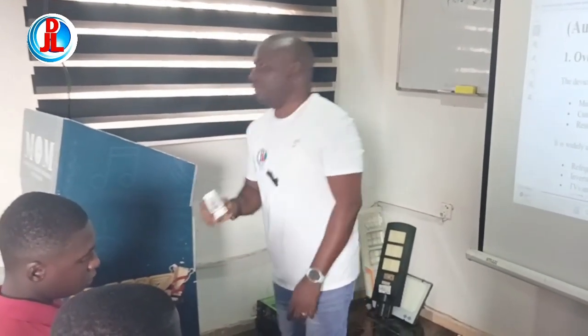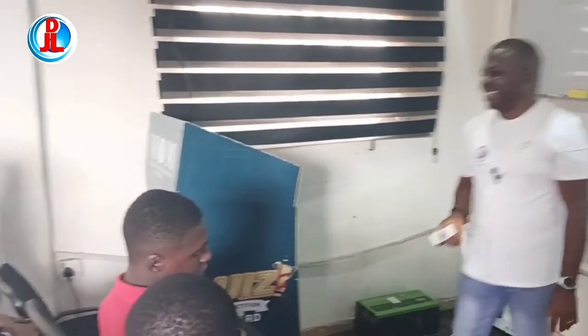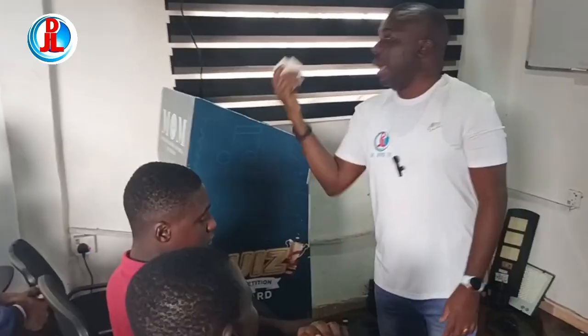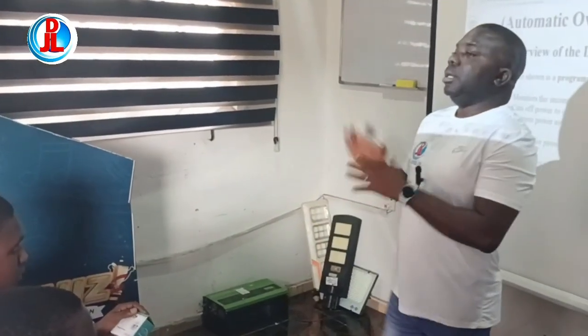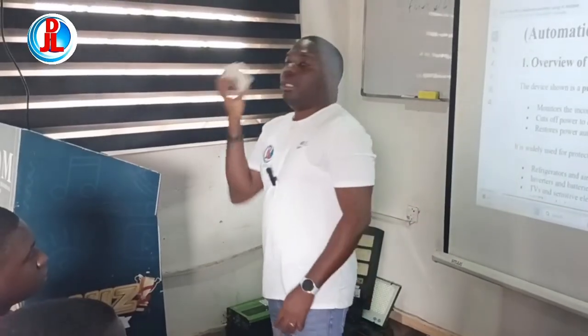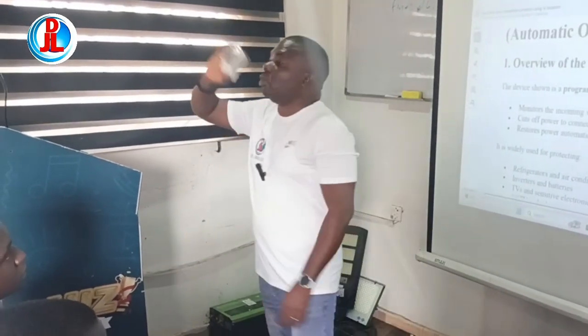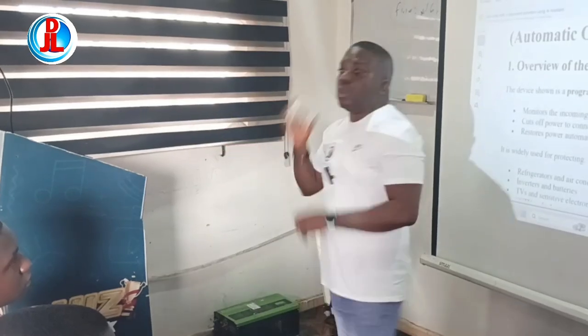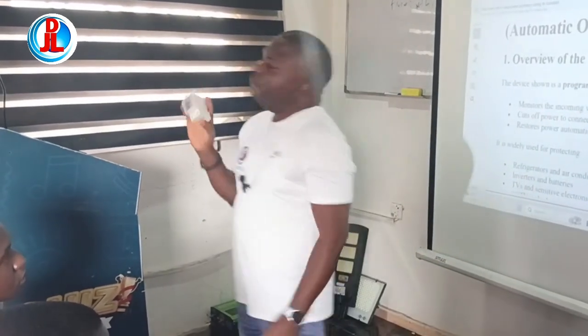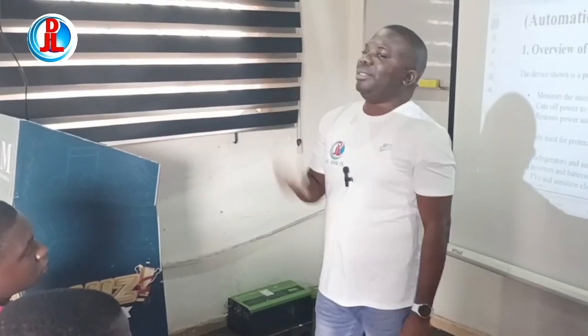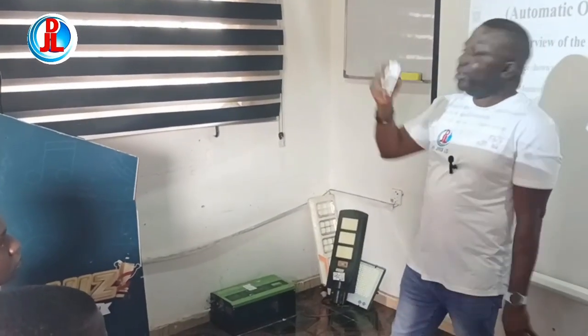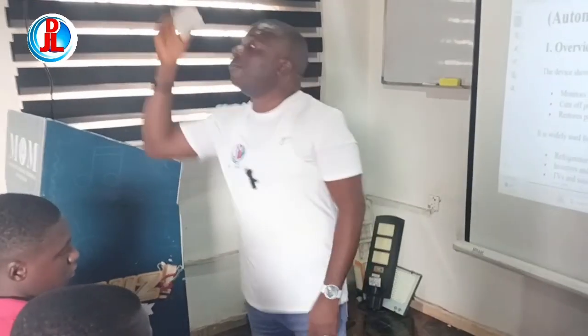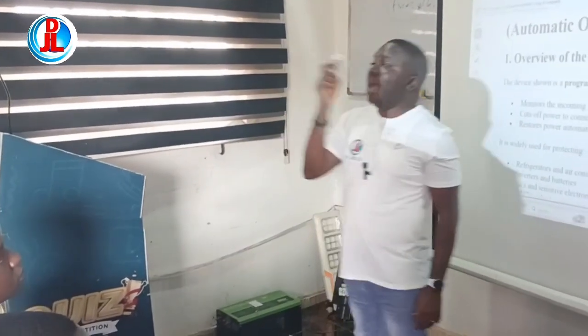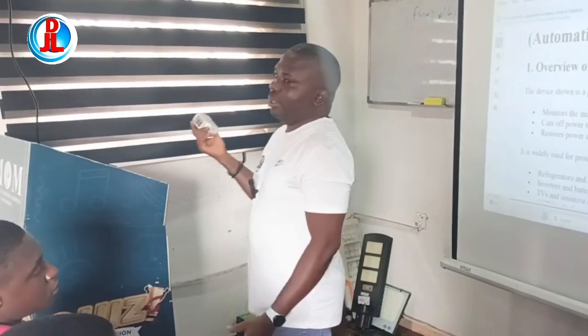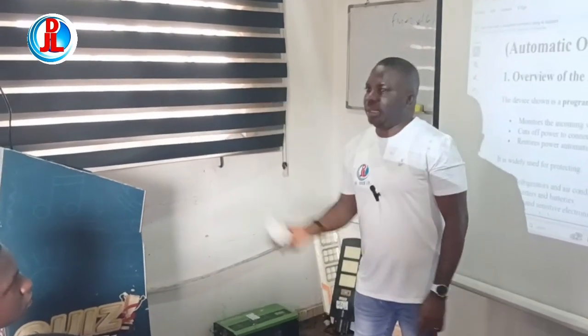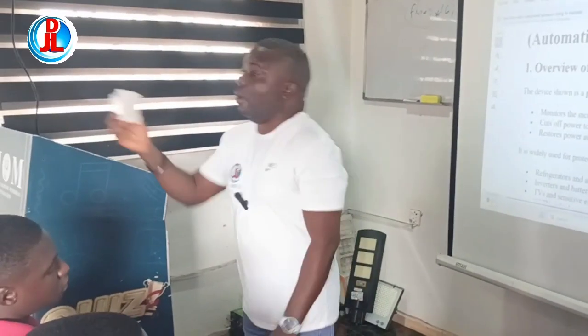Now you program it - so are you the one that programmed it? No. So assume that they did not program this, or even if they did, you set the program according to what you want. So anytime you get to site to install this, please check it. Like most of the places you are complaining about - go and check. You see that the voltage cutoff is 280, and at 280 flowing into the inverter, it damages the inverter. So you see this guy is not working - have you been able to get this guy to work for you?